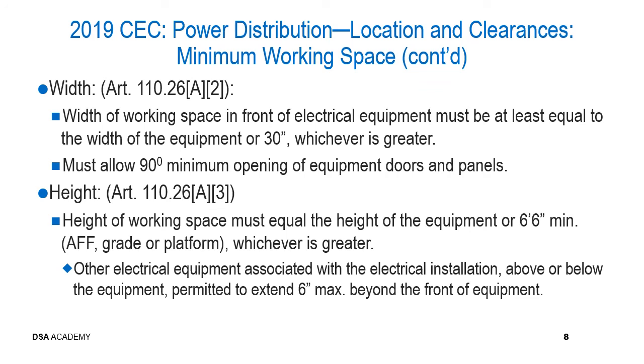And it's important to understand also that there's a slight allowance made in this minimum working height area, and that is that other electrical equipment that is associated with the electrical installation, either above or below the equipment, is permitted to extend 6 inches maximum beyond the front of the equipment.